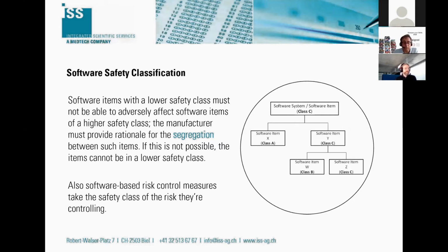Also, something to be aware of is that if you have software-based risk controls for anything, the risk controls take the safety class of the risk they're controlling.